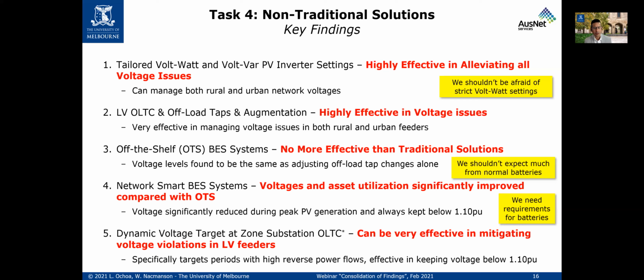The last non-traditional solution we identified, already used by AusNet and other DNSPs in Australia, is dynamic voltage target setting at substations. This uses smart meter data from remote parts of the high voltage feeders, or a proxy of the reverse power flows at the head of the feeder, to determine the amount of generation happening at a given moment, and adjust the voltage target of the substation accordingly.